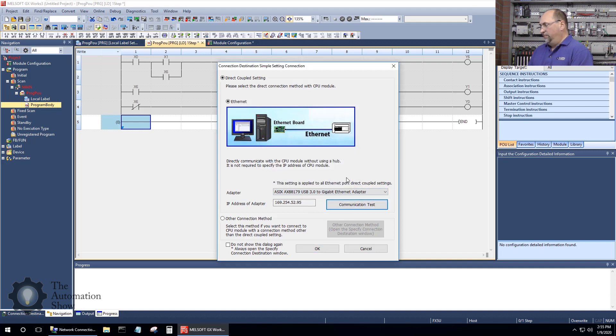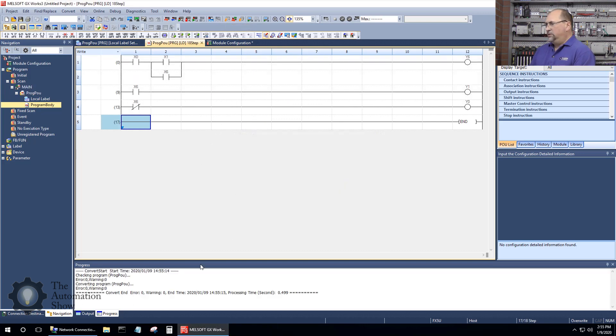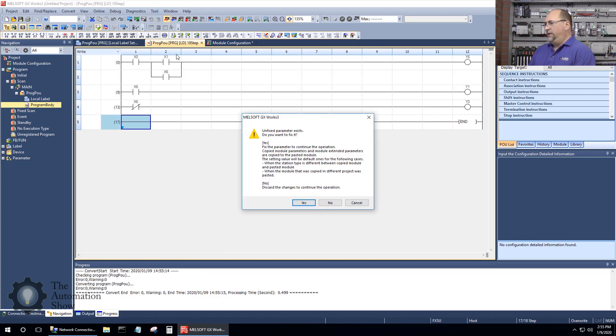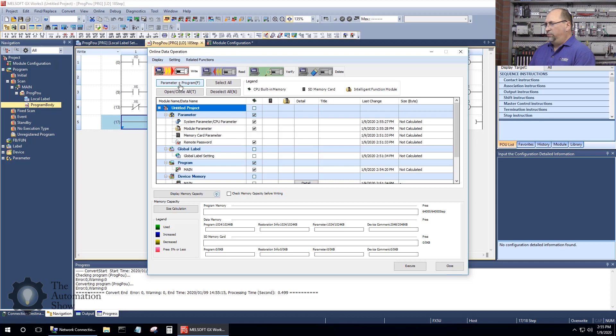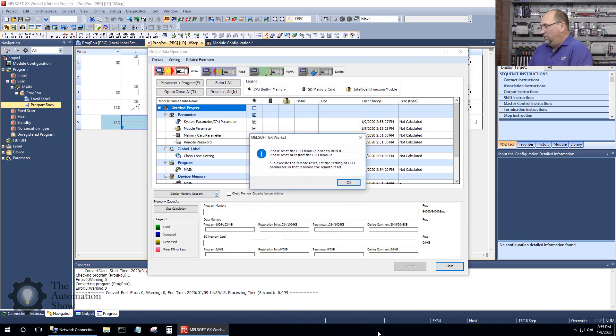We'll do a communication test — successful, I found it. I also want to build and convert the program to check for errors — no errors, no warnings, that's good. We're ready to download. I'll write to PLC. It says unfixed parameter exists — I'll say yes — and I'll choose all parameters and programs. If you're an expert and I'm doing this wrong, let me know, but this works well. Execute — download complete, close.